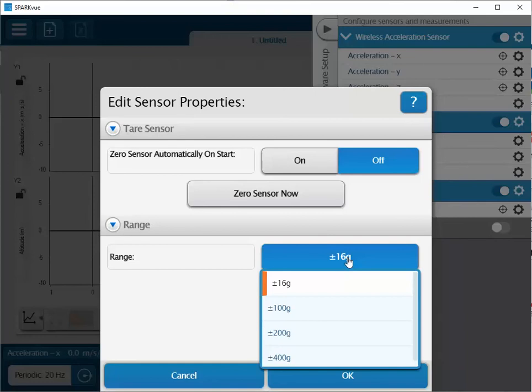For instance, if you collect data and find a flat line at 16 times the acceleration due to gravity or 16 G's, you've likely maxed out the sensor and need to select the next range up.